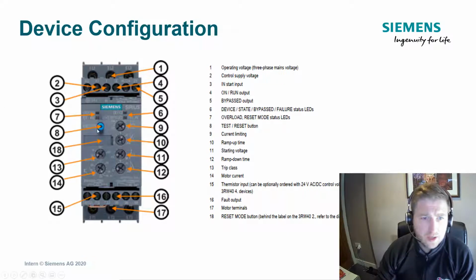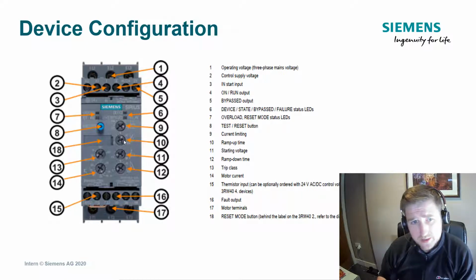So it's really critical in the selection process to get this potentiometer correct to ensure that the motor is going to be able to start up. The pot below it here is for the ramp up time, so that can go from 0 to 20 seconds dependent on the time that you desire. It's not an accurate potentiometer. Soft starters aren't meant for precise starting and stopping times, so it's a rough estimation as to how long it'll take that device to run up to full speed.